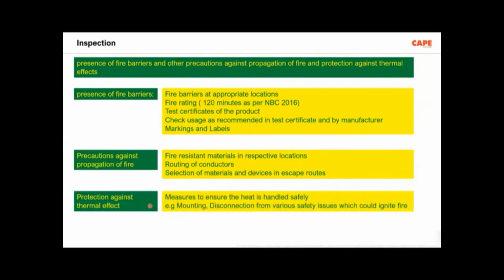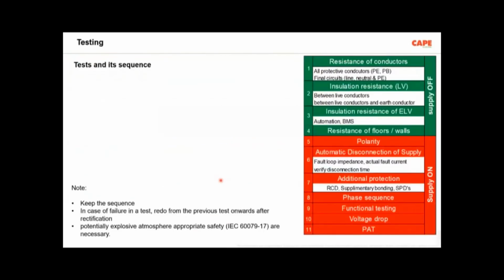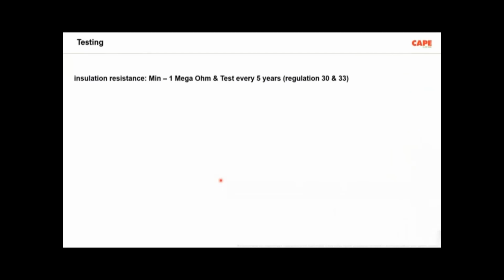Number 3, protection against thermal effect. As I said, you will have some equipment which is producing heat. Have you installed that equipment in such a way that the heat produced inherently because of its operation is not destroying the neighboring installations? So all these 3 parts come under fire inspection. The sequence: fire barriers with 5 parts, precaution against propagation of fire, and protection against the thermal effect. All the 3 are important. Now, with the coordination of the testing and the inspection, as per the upcoming National Electrical Code as well as the guide, we will have more clarity on this subject.